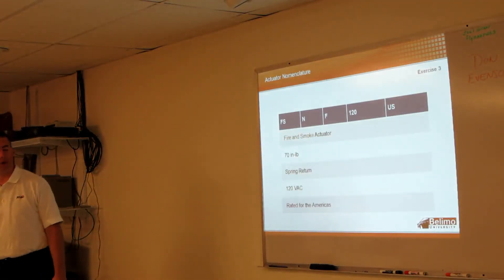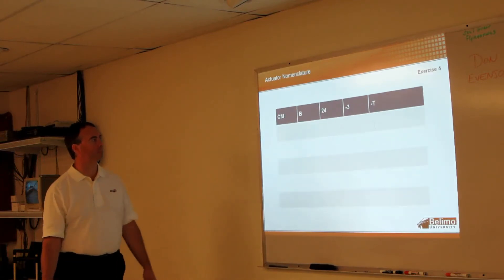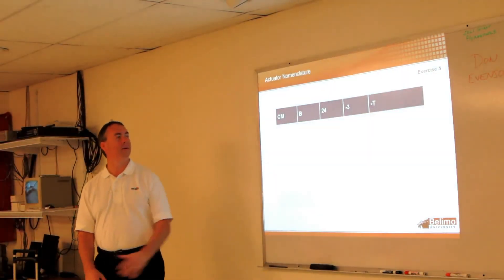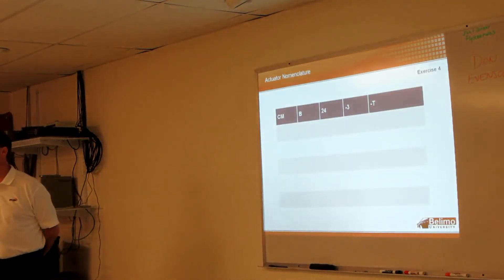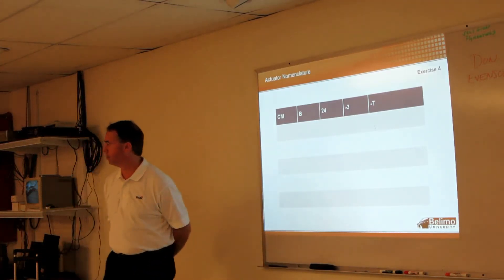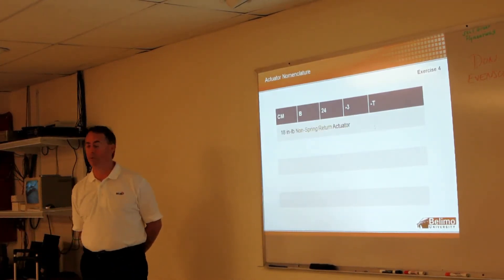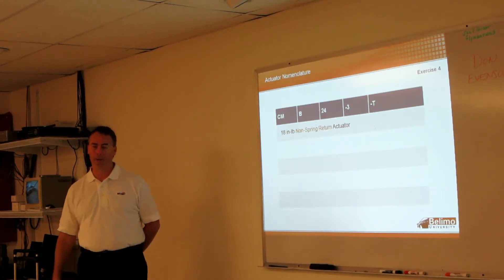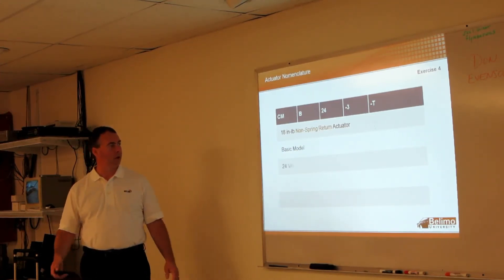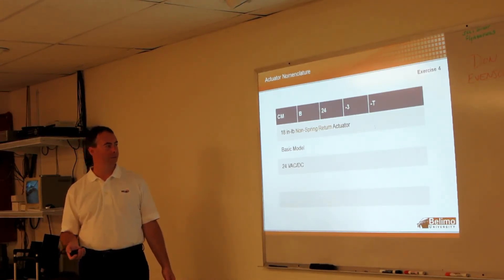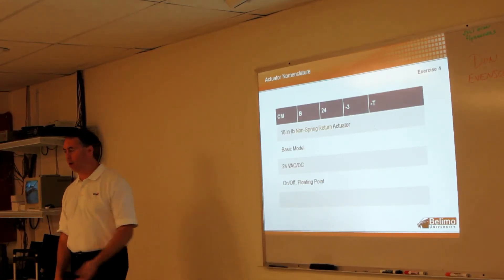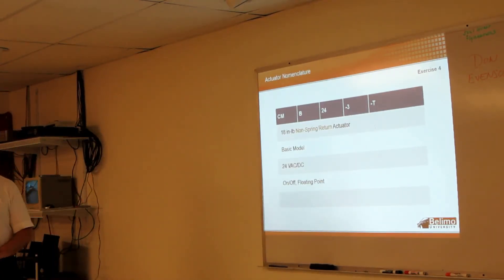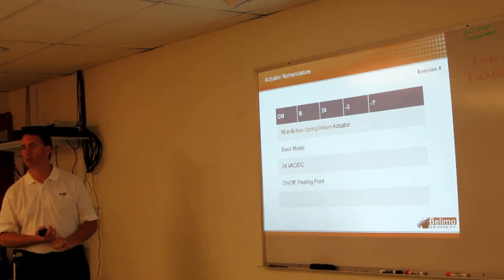I think this is the last one. CM - we didn't really mention CM but it's in there. Right, non-spring. 18 inch-pound non-spring. The B? 24 volt. Dash 3? Control. Yeah, floating control or on-off. With our non-spring actuators, the dash 3 serves both our floating and our two position. Dash T option? Terminal strip.